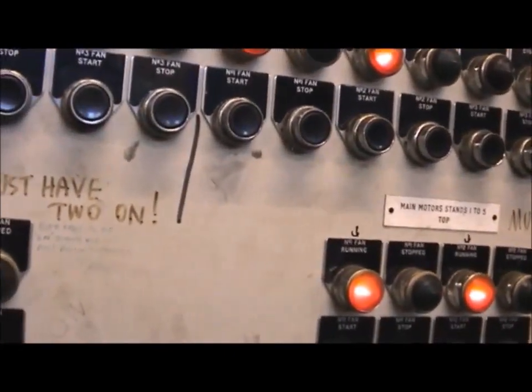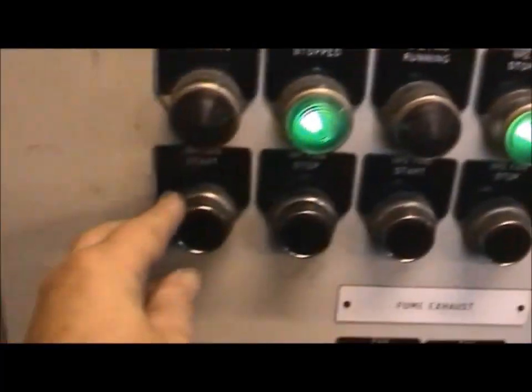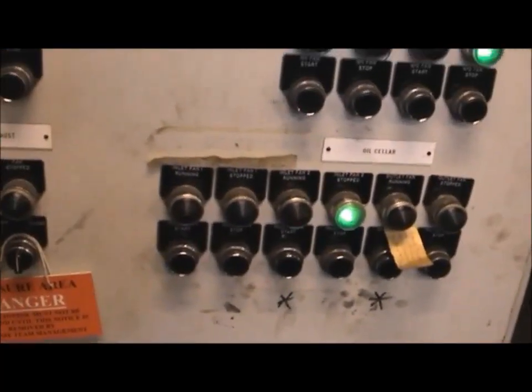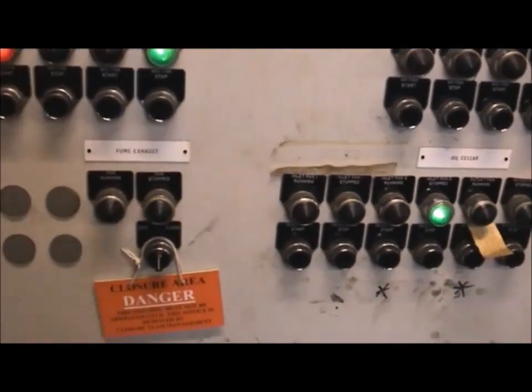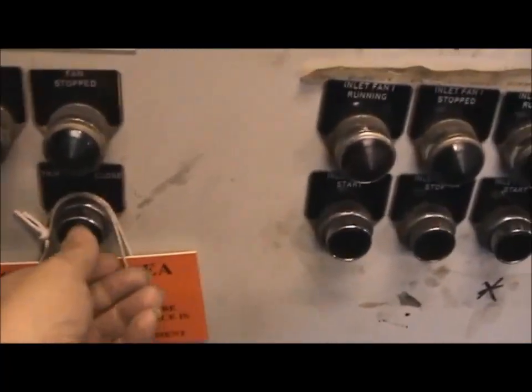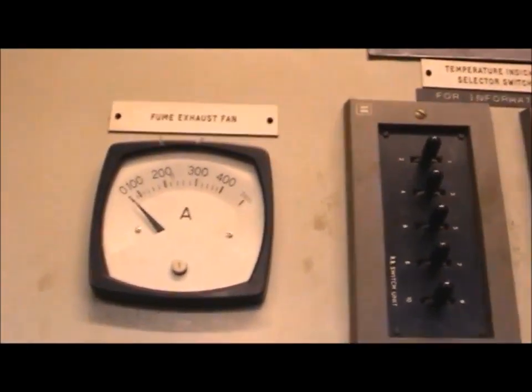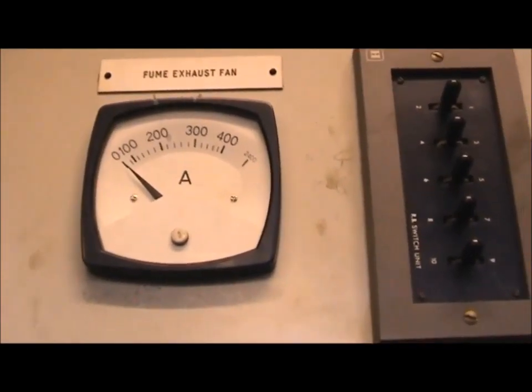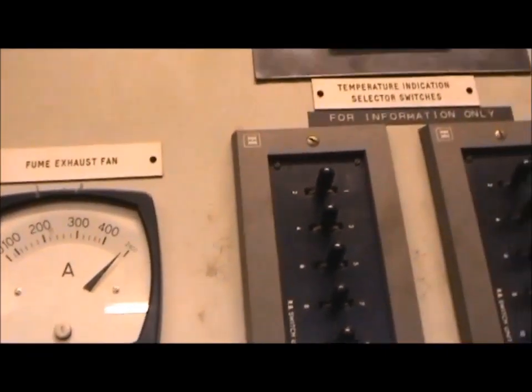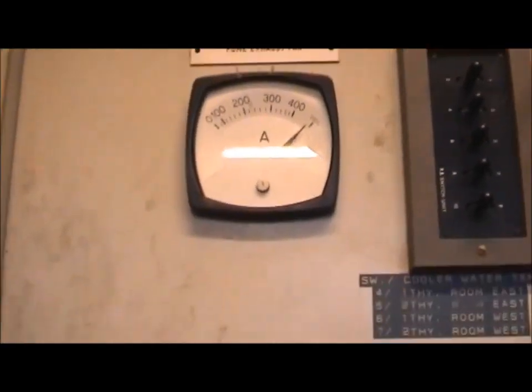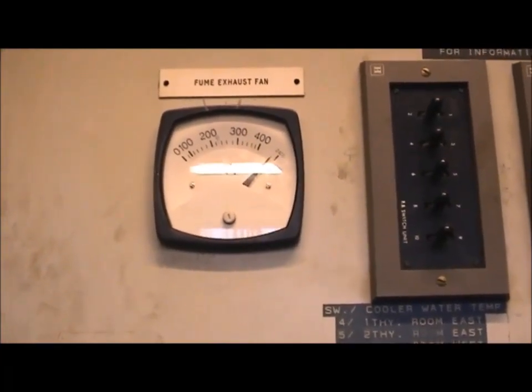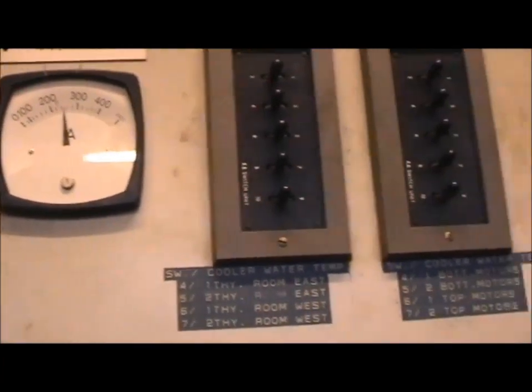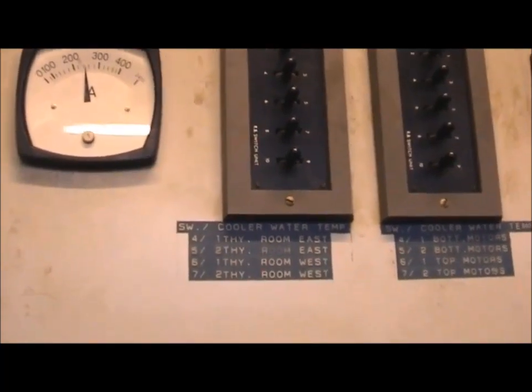Carry on, screw down ventilation fan, start that. We don't need the air makeup, we don't need the oil cellar. Now this is the big monster to remove the oil mist from the system. We're going to close up this. You see the current zooms around there, you'll hear it start. That's a fume extract fan. Hangs there for a while. Hopefully that's it, belts are slipping, pull back to its normal running value. So that's running.